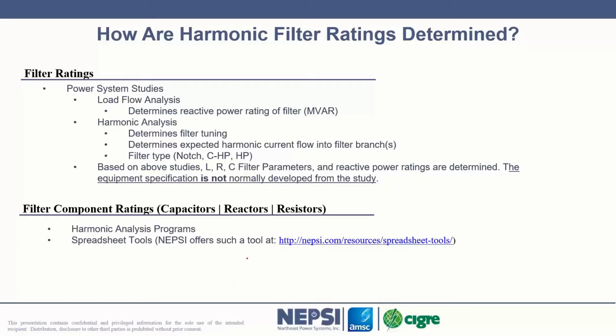So once you have a harmonic analysis complete, the next step normally is to come up with what capacitors, what reactors and what resistors I should use. You have to come up with voltage ratings, current ratings, watt ratings and kVAR ratings of these devices. And that's not typically done with a harmonic analysis. It's typically done with a spreadsheet tool. So the filter design is determined by harmonic analysis, the choice of tuning point, the type of filter. But in the end, you're typically using some type of spreadsheet tool to come up with those values.